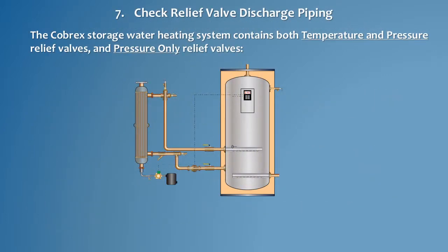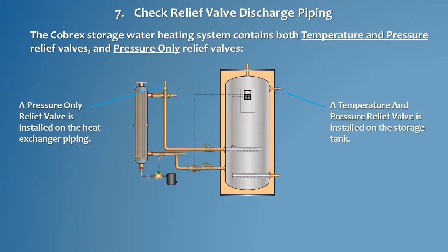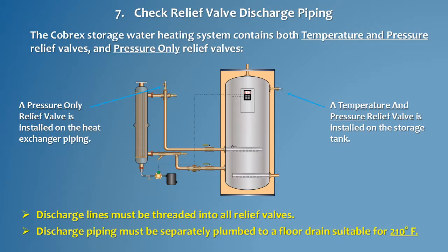The Cobrex storage water heating system contains both temperature and pressure relief valves and pressure-only relief valves. The temperature and pressure relief valve is installed on the storage tank, and the pressure-only relief valve is installed on the heat exchanger piping. Check to ensure discharge lines are threaded into all relief valves and that each relief valve discharge piping is separately plumbed to a floor drain suitable for 210 degrees Fahrenheit.